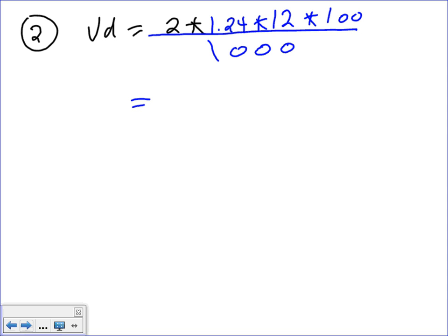Yes, sir. What if you wanted to do this equation for number 2 but include number 1? Do you have 2 different amps? You can't include the distance, because if you go all the way to the building, what's your amp? 12? No, because at one section the amps were 12, at another section the amps were 14. Very good point. Why do I have to sectionalize it? Because at one section the amps were 12, at another section the amps went up because we get closer and pick up more lights. Does that make sense? Yeah, that's why I can't use it.